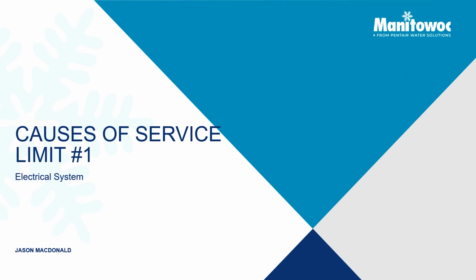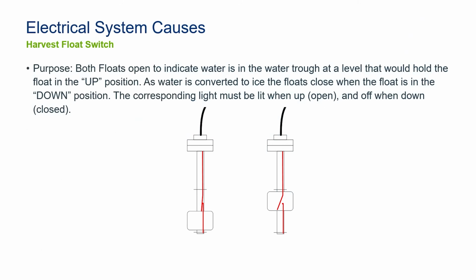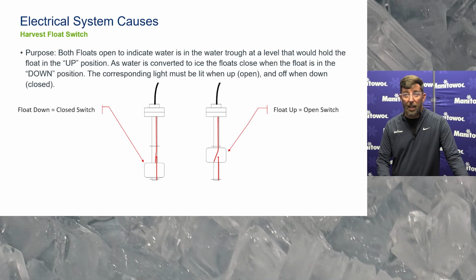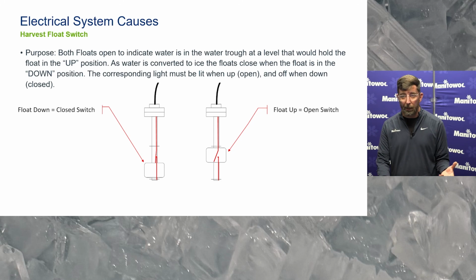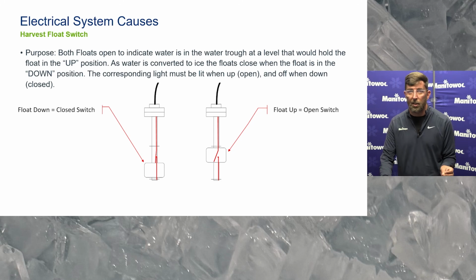What about the electrical system? Things in our electrical system can also lead to this. So we have float switches. This is a water sensing system. This ice machine senses water. It does not sense ice on the evaporator like other machines, whether we're talking about Indigo that uses an acoustical probe, or the old S model that was a water sensing probe. This doesn't sense ice, it senses water.